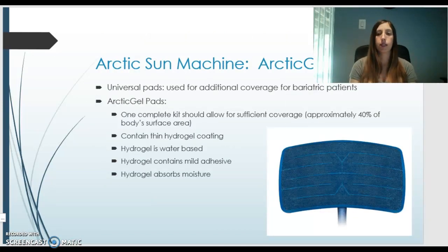The universal pads, as I said, are used for additional coverage for bariatric patients. The Arctic gel pads, 1 complete kit should allow for sufficient coverage, which includes approximately 40% of the body surface area. They contain thin hydrogel coating. The hydrogel is water-based, contains mild adhesive, which is best for the skin.